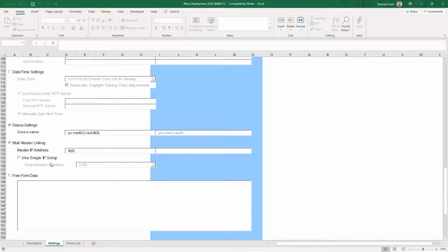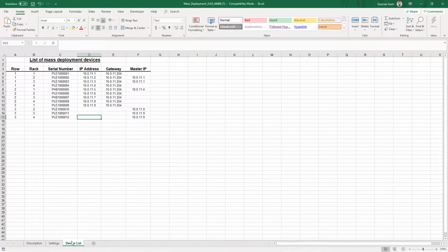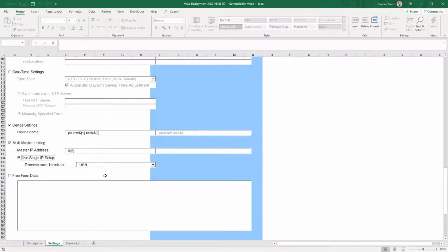We view column 6, which will be F here. And if we want .2 to report to PDU.1, we can put those IP addresses here and link those together. This is really beneficial for a port forwarding installation, a single IP setup as we're going to call it, because you're not actually going to be able to access those ports in the link setup. So we could check this box, use single IP setup, and then select our downstream interface.